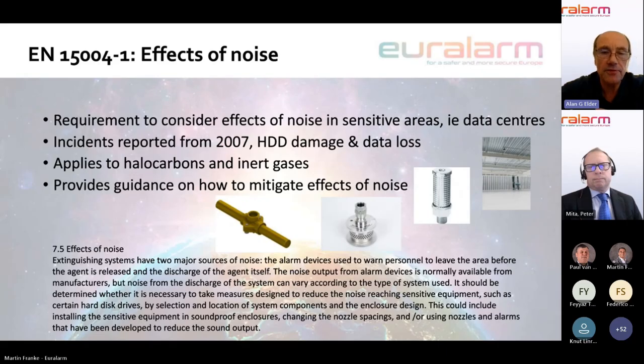Typically, the output from the alarm devices is available from the OEMs of those alarm devices. But noise from the discharge of the system can be very significant, according to the type of system used, the discharge time of the system, the proximity of the discharge devices to equipment such as the hard drives, and also whether that equipment itself has any form of noise damping.